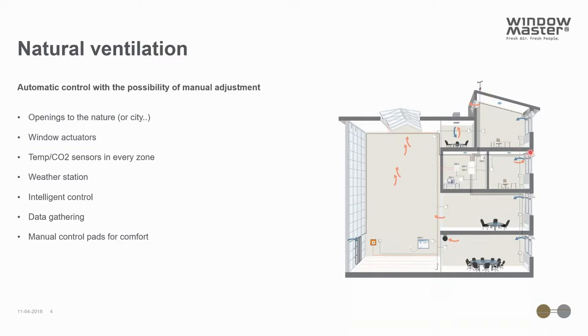The question is: how much air can you achieve through the window openings for a project? How large an air change rate can you really get? This will depend on which ventilation principle you're working with. For the same opening area you can achieve a much larger air change rate for cross ventilation compared to a single-sided ventilation system, so it's very important to take into account which strategy you're using in your calculations.